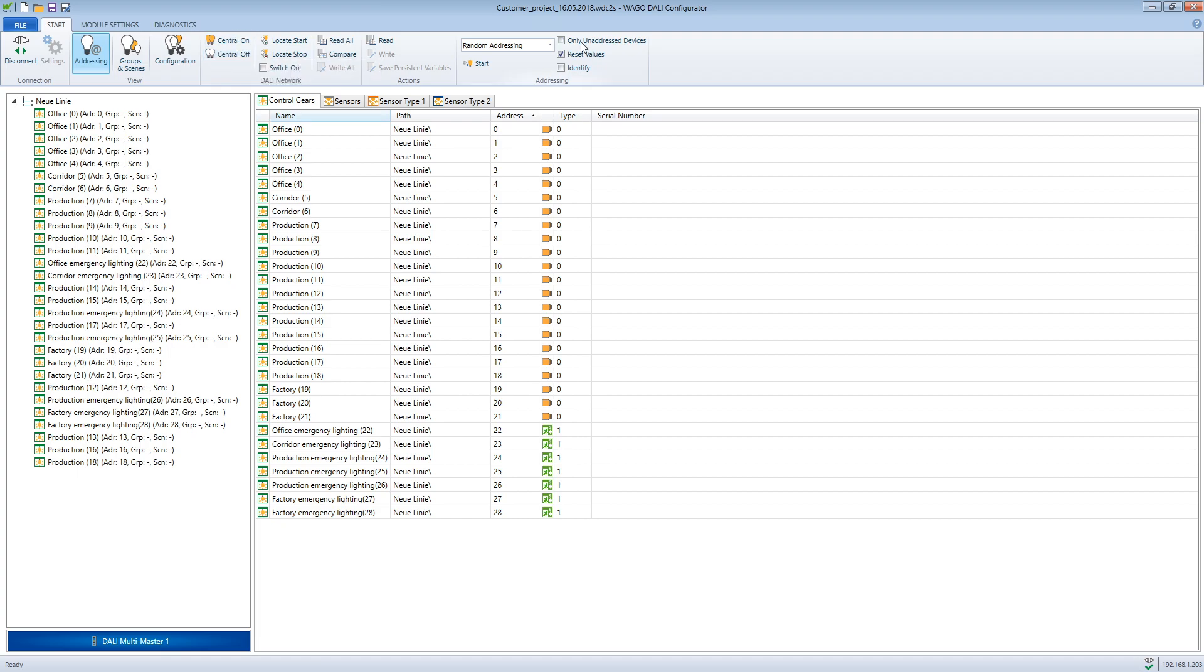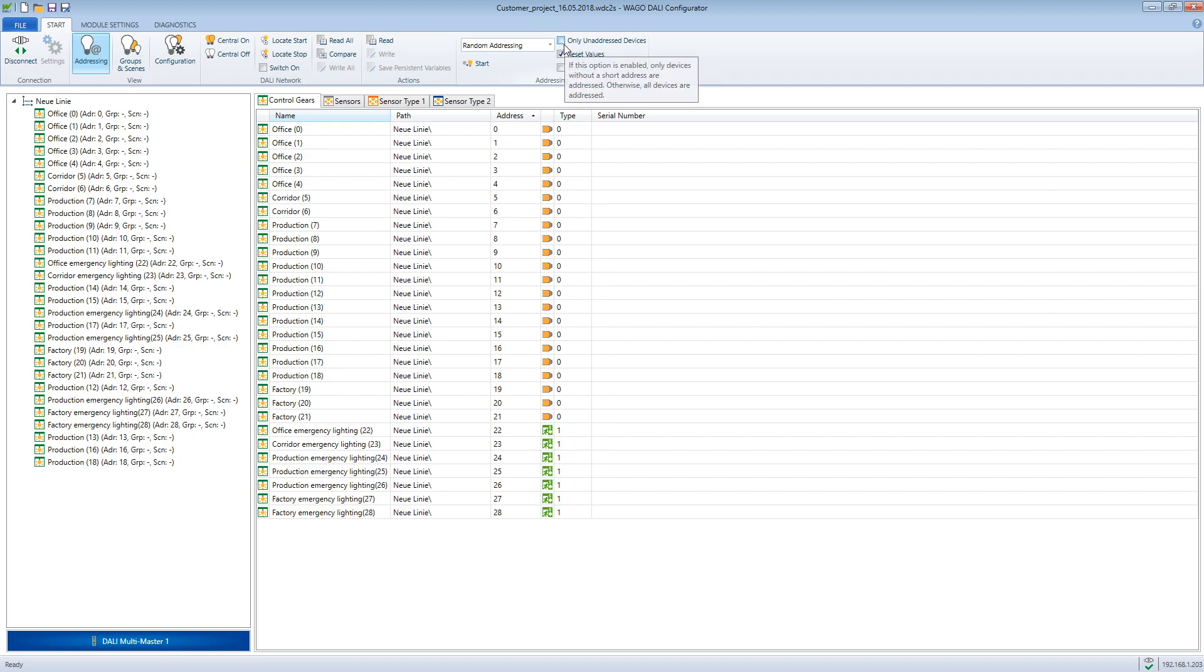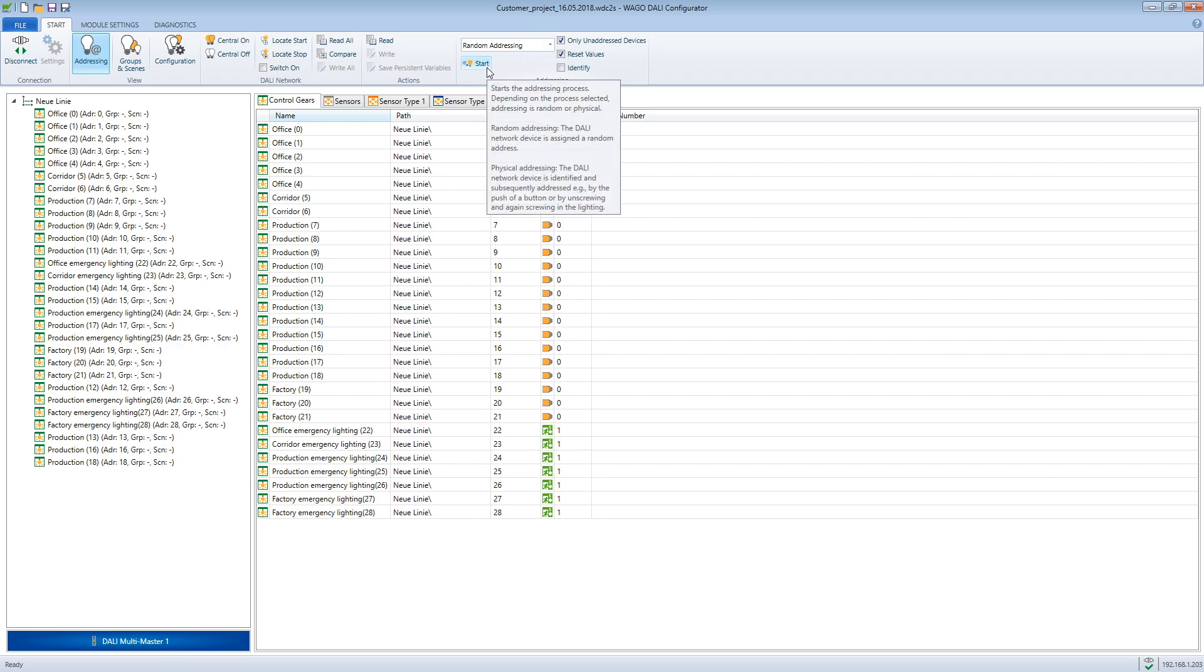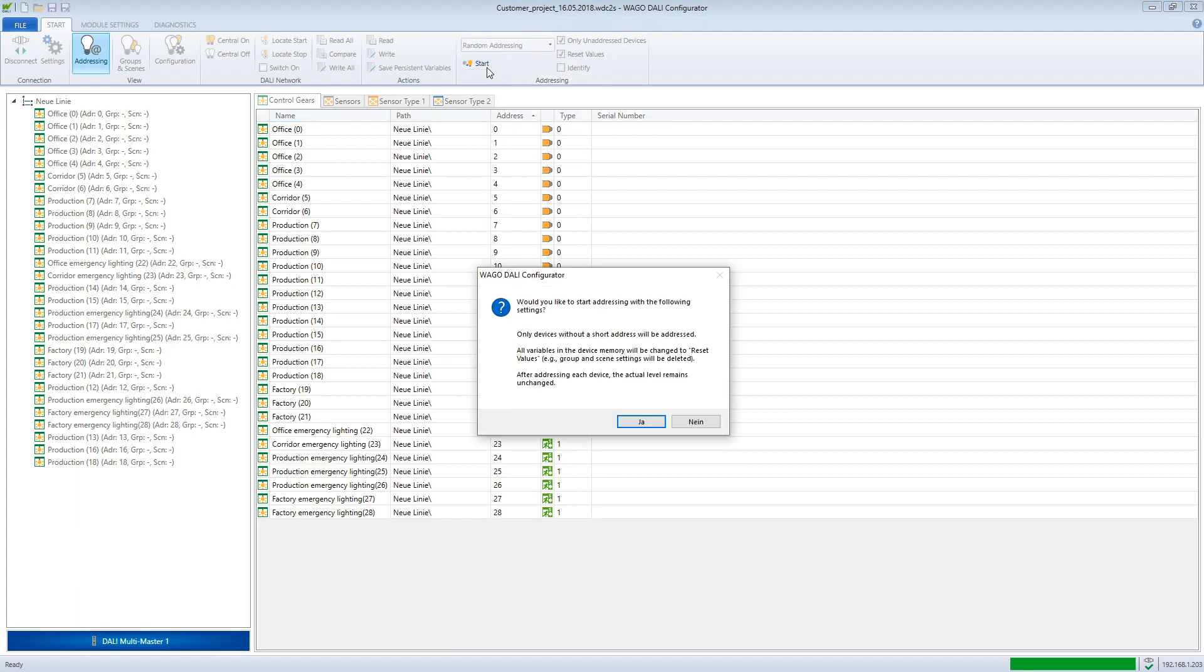After making sure that all operating devices on the bus react, we move on to addressing. Here the only unaddressed devices box must be checked, otherwise all devices will be readdressed. Then we can start the addressing.